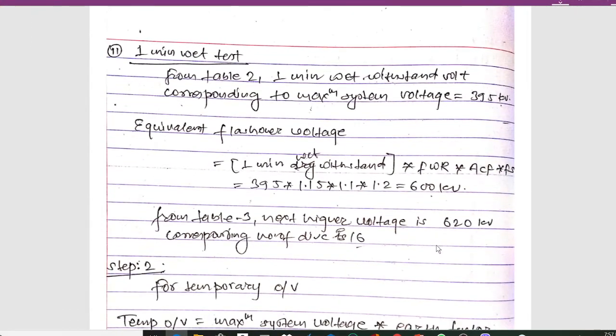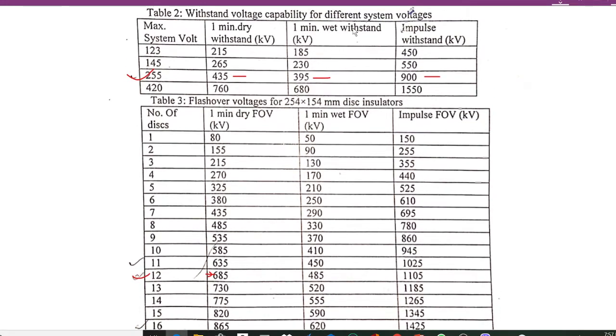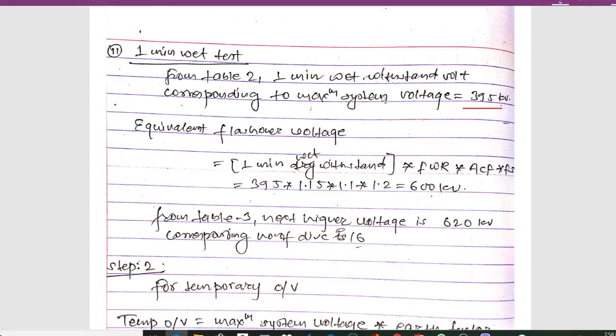For the one-minute wet test: from Table 2, the one-minute wet withstand standard voltage corresponding to maximum system voltage is 395 kV. The equivalent flashover voltage formula is: one-minute wet withstand standard × FWR × ACF × FS. Substituting 395 × 1.15 × 1.1 × 1.2, we get 600 kV.